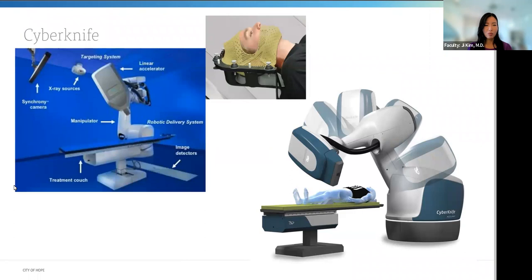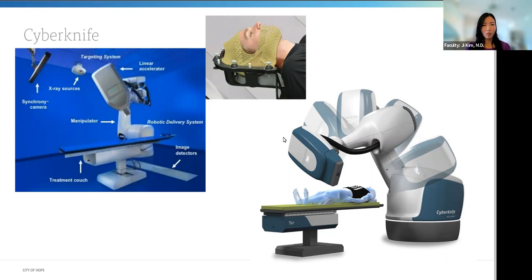Another machine often used for SRS is the CyberKnife — a LINAC on a robotic arm. Created as an alternative to Gamma Knife, without the need for a frame or cobalt-60. CyberKnife was invented at Stanford and first debuted in 1994, cleared to treat intracranial tumors in 1999, and tumors anywhere in the body in 2001. The original CyberKnife models used cone-based collimation, whereas the newest model uses MLC-based collimation and is much faster than previous versions.